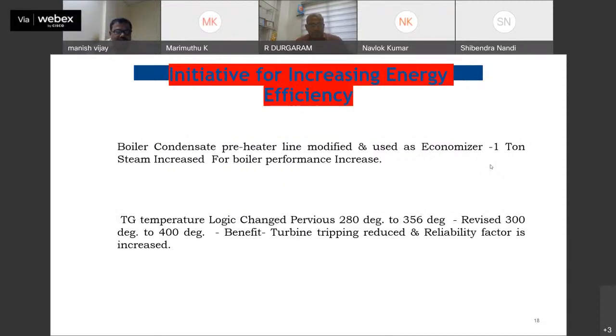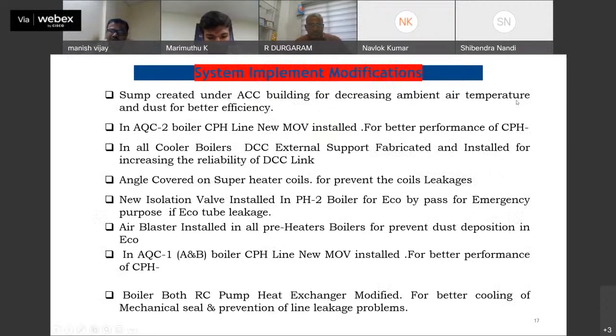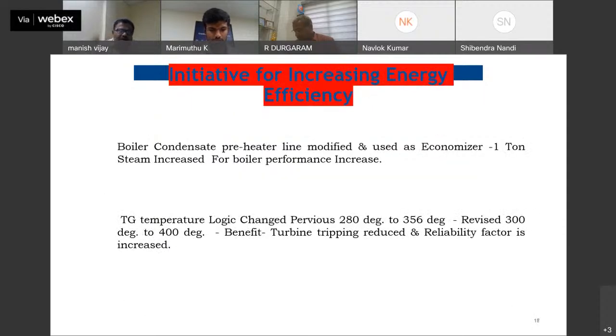Air blaster installed in all preheater boilers to prevent dust deposition in the eco coils. In AQC A and B boiler CPH line, new MOV installed for better performance of CPH for operation purpose. Both RC pump heat exchangers modified for better cooling of mechanical seal and prevention of line leakages and problems. Boiler condensate pre-heater line modified and used as an economizer, and 1 ton steam increase, so boiler performance is increased. TG temperature logic changed from previous 280 to 356 degrees, revised to 300 to 400 degrees centigrade. Benefit: turbine tripping reduced and reliability factor is increased.